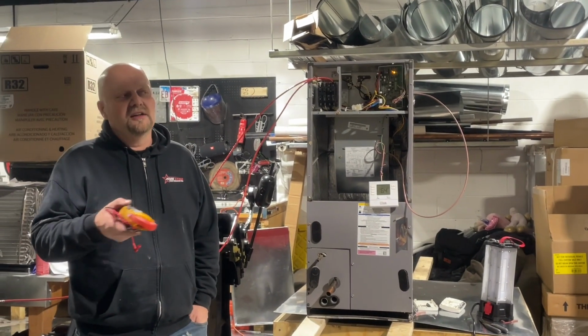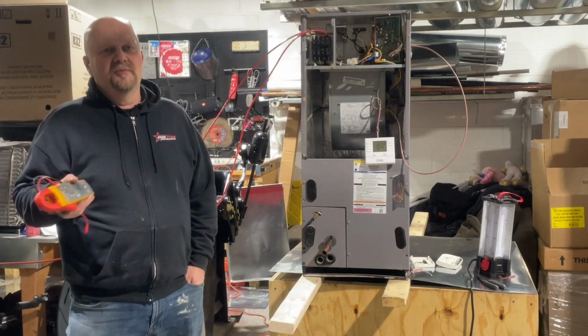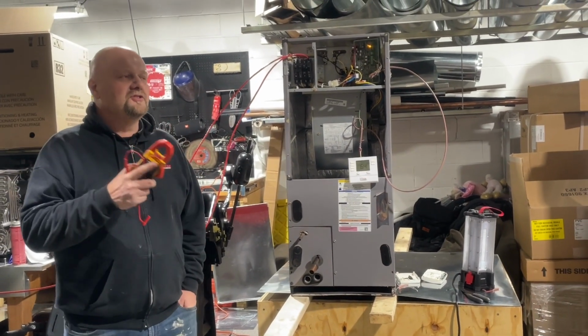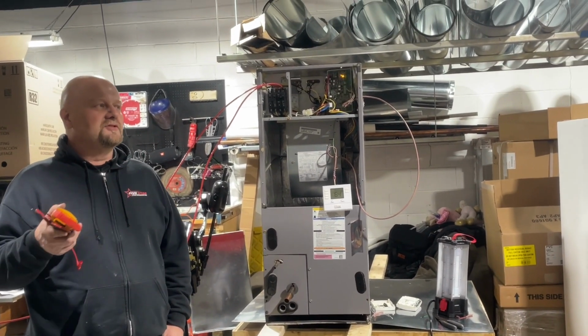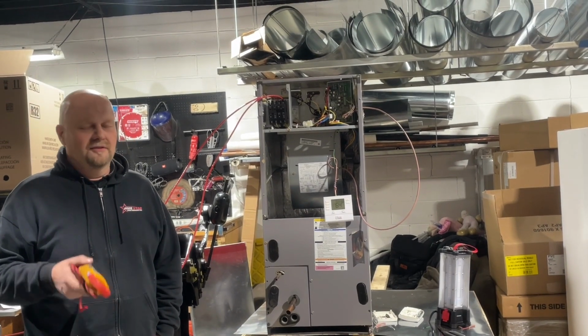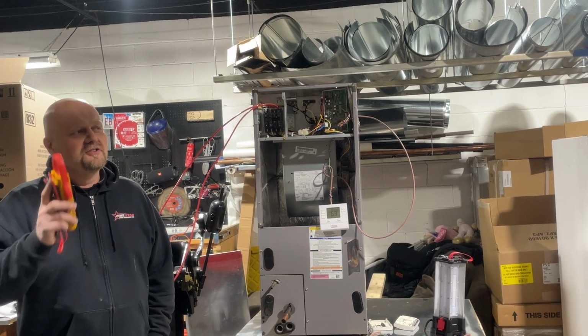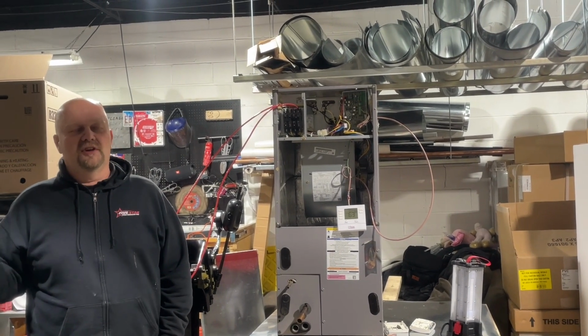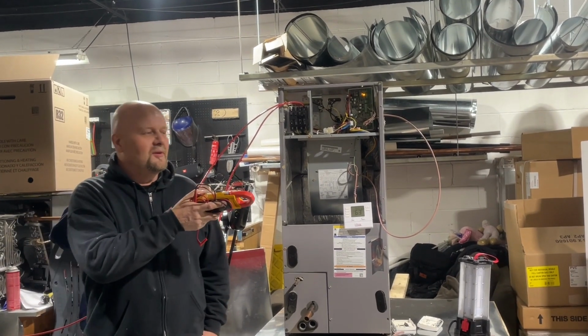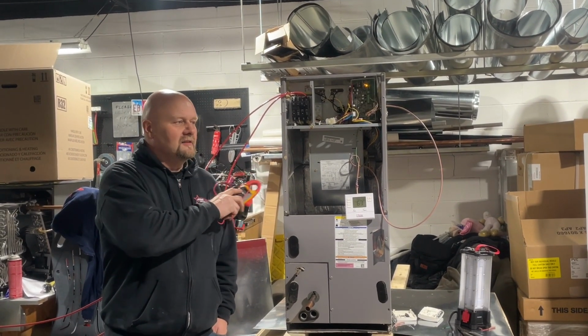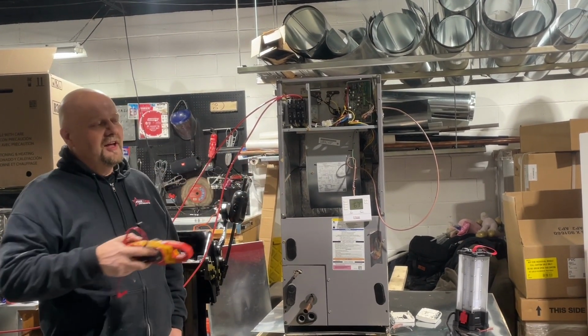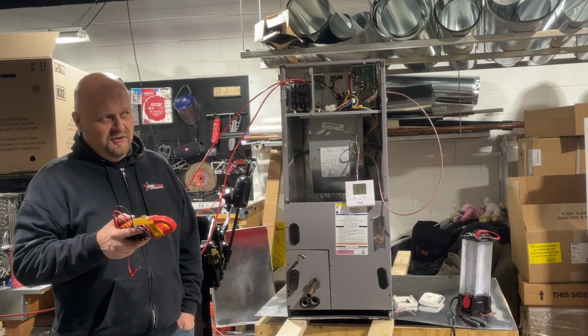A kilowatt is a lot. So now, just so you guys remember, roughly, each kilowatt is 3,500 BTUs. It's rough. Okay, so 3,500 BTUs equals a kilowatt. So now, what is the number that we had before? Not the one I just told you. 9.4. You go 9.4 times 3,500.